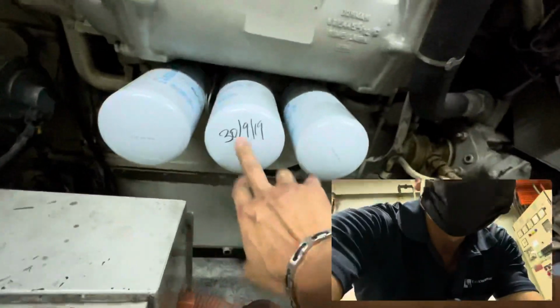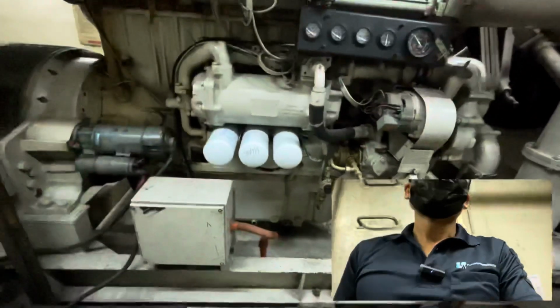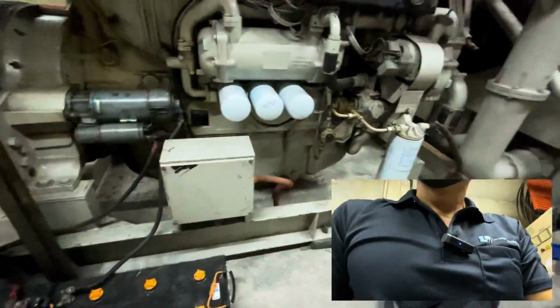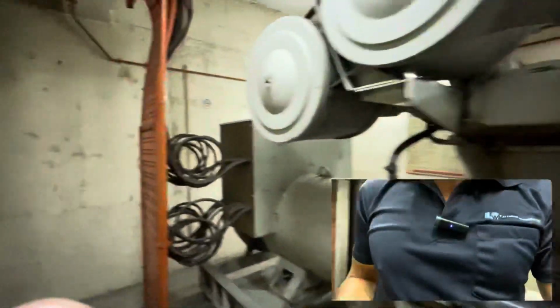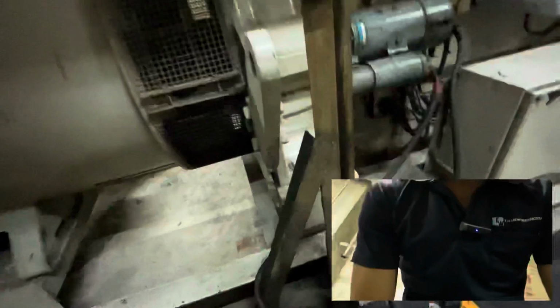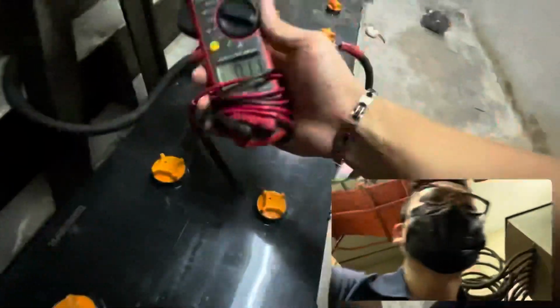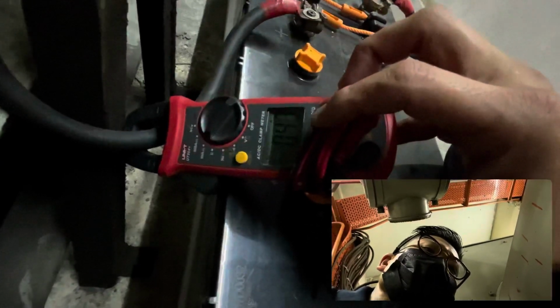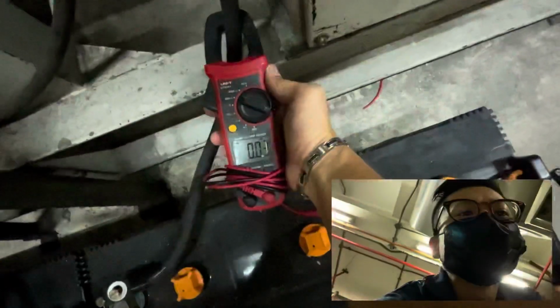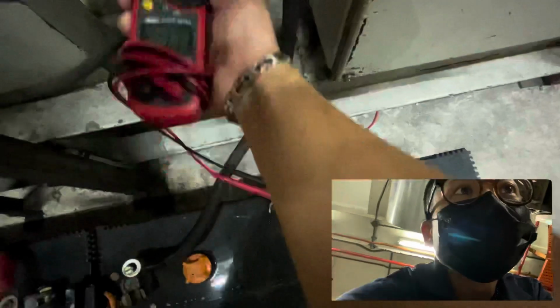Last service, 30th September 2019. Almost 3 years plus. Okay, how do we know the genset is charging? We're going to use a DC clamp meter. Let's check the charging current. This float charge, 0.4 amp. Okay. Oh, can you see from here? Quite low.